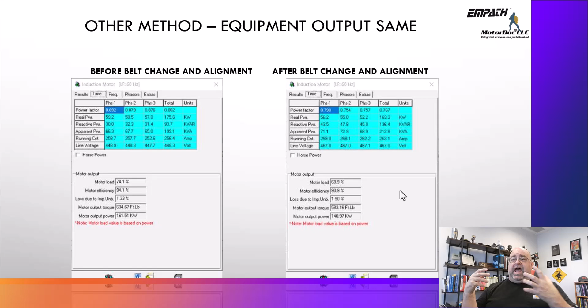So in this case, 175 to 163. This is a real application - we had 10 D belts, huge sheave, breaking shafts every few months. There was a big push to fix that. So I went back and said, here's the projected energy we can save by going to 2V belts, slightly larger sheaves, which reduced the overhung load on the shaft, less chance of breaking it.